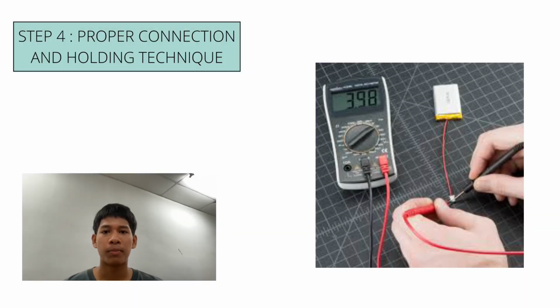Step 4. Proper connection and holding technique. Step 4 is about proper connection and how we hold the probes. Always connect the black probe to the COM terminal and the red probe to the correct terminal according to measurement. When holding the probes, keep your fingers behind the finger guard. Never touch the bare metal tip during measurement, especially when dealing with high voltage. Also, make sure the probe tips do not accidentally touch each other, because this can short the circuit.